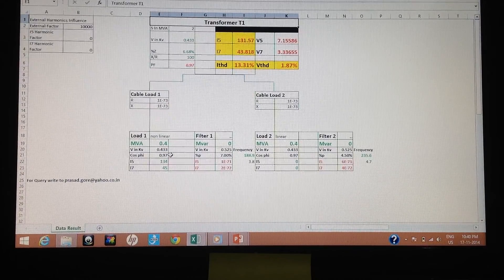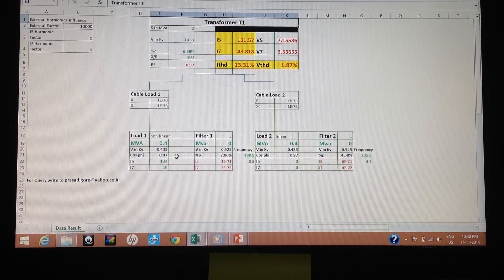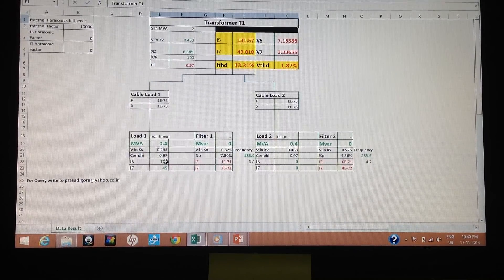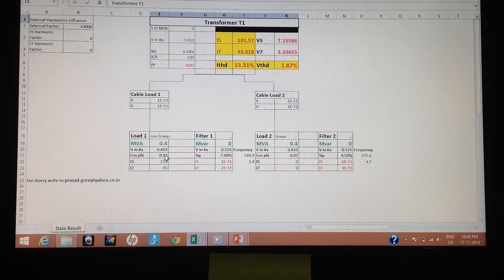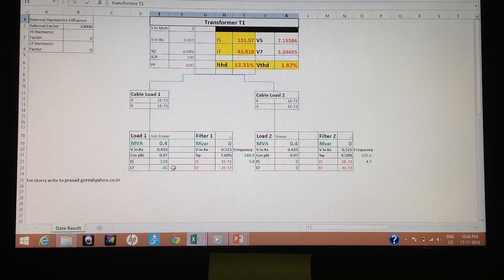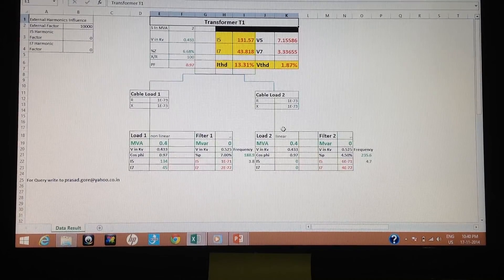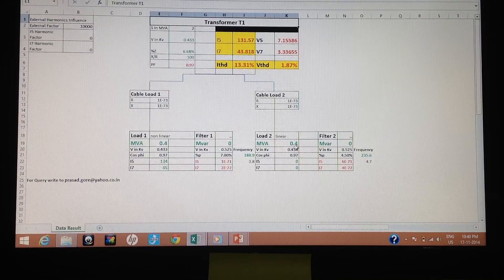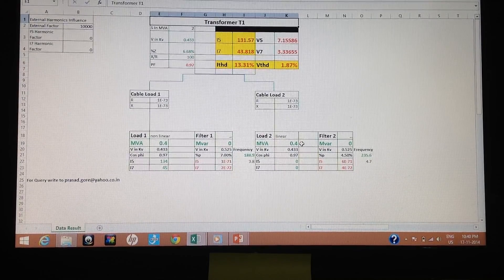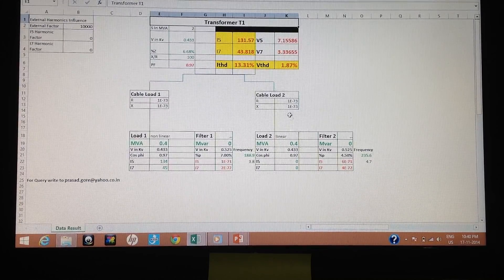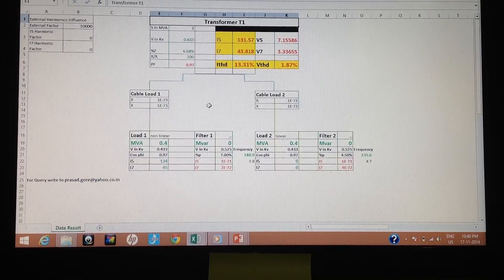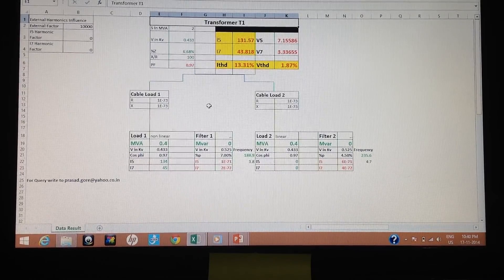Because of these two loads, you get the required load. Load center 1 is a non-linear load, injecting 134 amperes of 5th harmonics (I5) and 45 amperes of 7th harmonics (I7). Load center 2 is a linear load having no harmonic content, with a connected load of 0.4 MVA at power factor 0.97. The KVAR requirement comes to around 0.186.